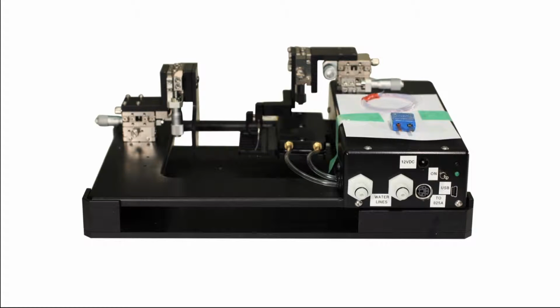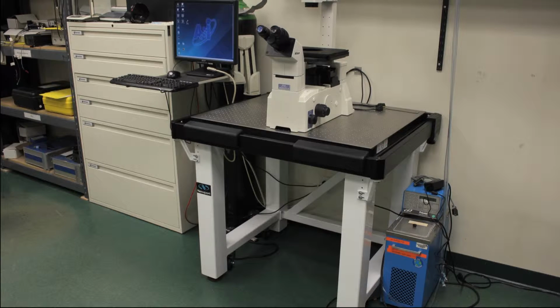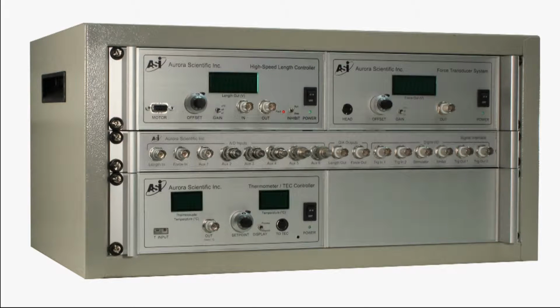Once unpacked, you will need to select an appropriate location to set up the instruments. The 802D Permeabilized fiber apparatus is designed to mount on an inverted microscope, but can also be used on the lab bench with just a dissection microscope. A vibration isolation table is recommended, but is not required. Space for the control electronics is required within 2 meters of the apparatus, either in a 19-inch rack or on a nearby shelf.